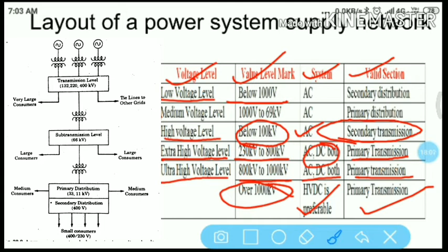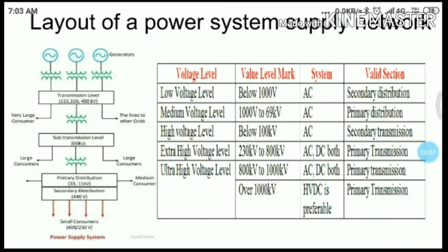The system in which electrical power is distributed at secondary distribution level employs a three-phase four-wire system. The three-phase wires consist of three lines: red, yellow, and blue. The voltage between any two phases is 400 volt and the voltage between any single phase and neutral is 230 volt. An AC supply obtained from only one line and the neutral conductor is called single phase supply.